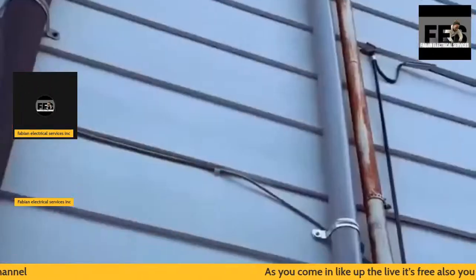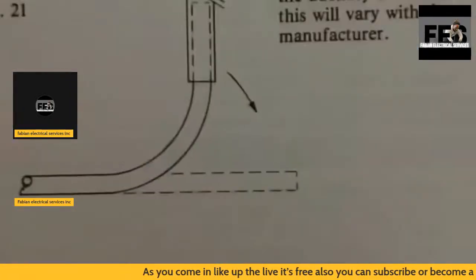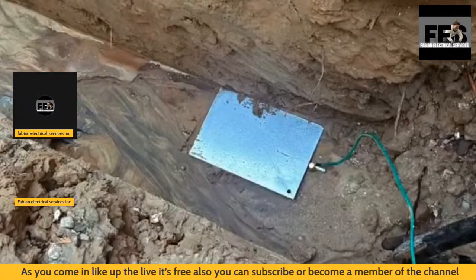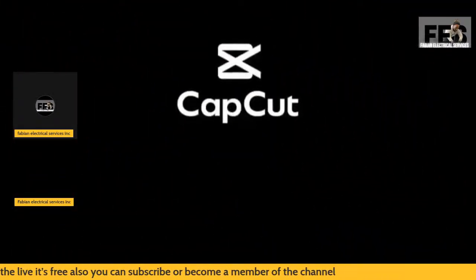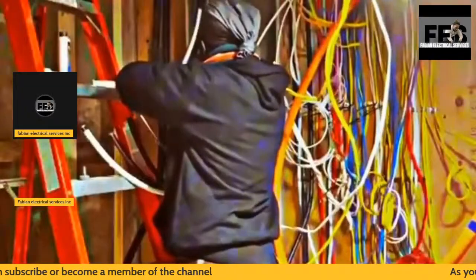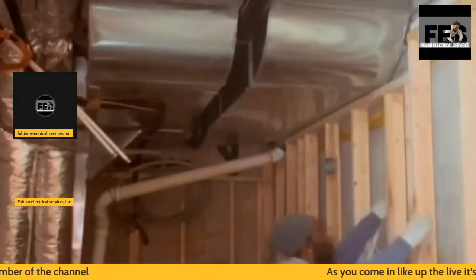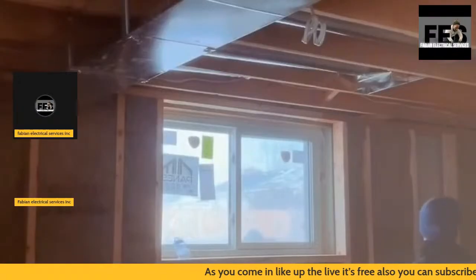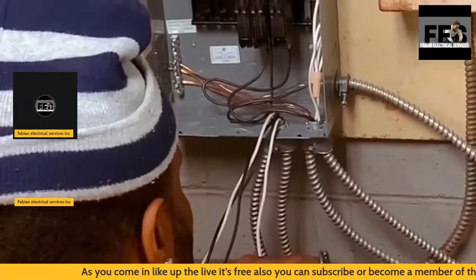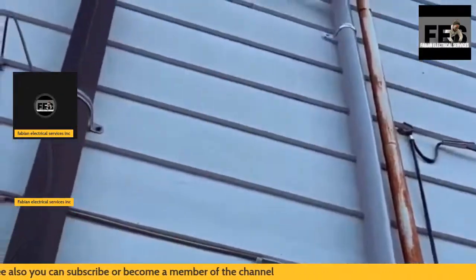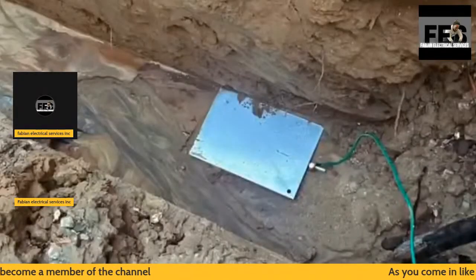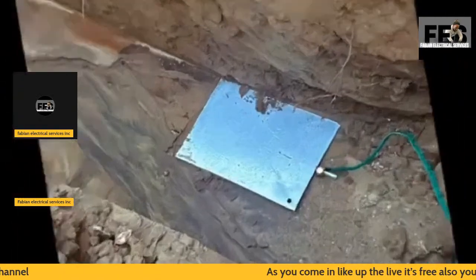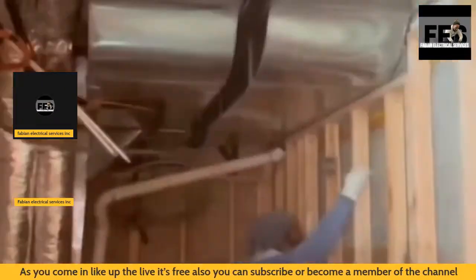Why do I do it? Well, it's in the Ontario Electrical Code. It says that all cables have to be strapped down by some means of support, whether it be staples or tie wraps. Even when it comes to electrical conduit, there's another code rule in there for the installation of the conduit. It should always be strap supported.